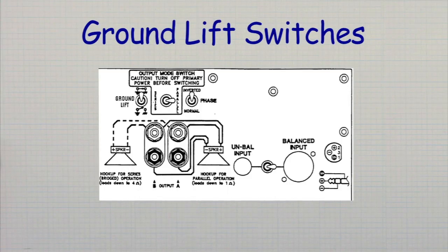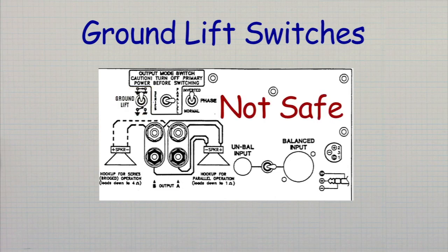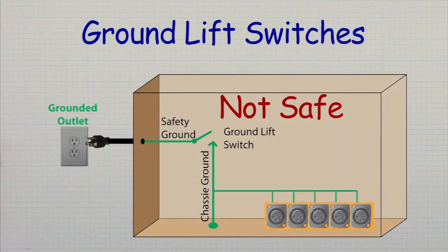Ground lift switches can be found on some professional audio equipment. These switches work in one of two ways. In the past, the ground lift switch would disconnect the safety ground, the one from the AC cord, that goes to the chassis ground, thus preventing any ground loops. But this also makes the equipment unsafe by disconnecting the safety ground.